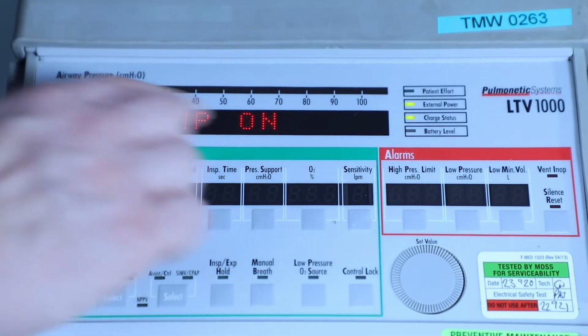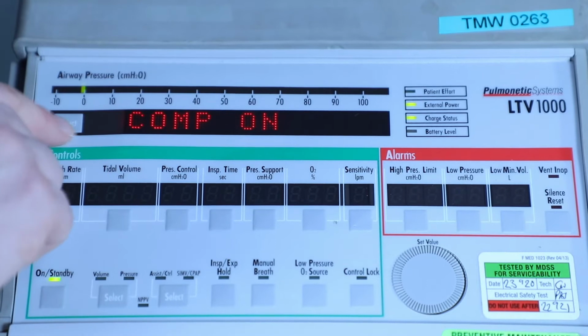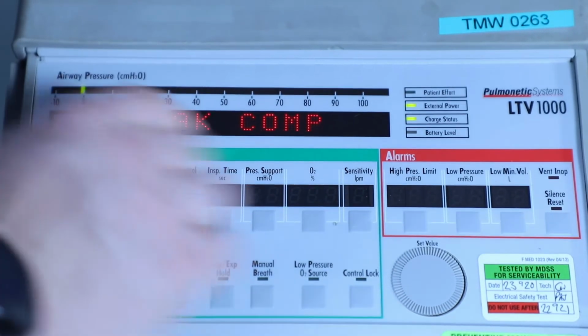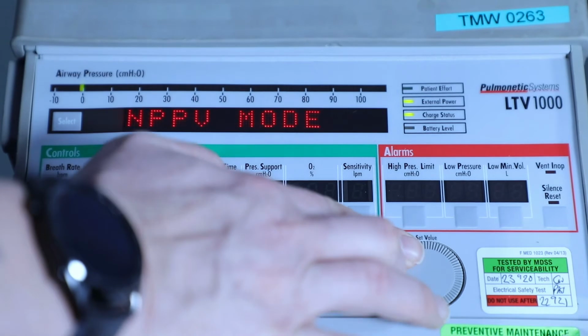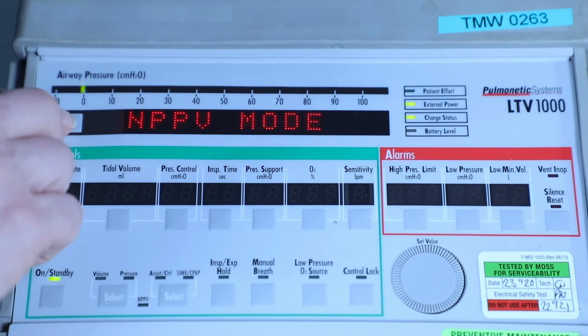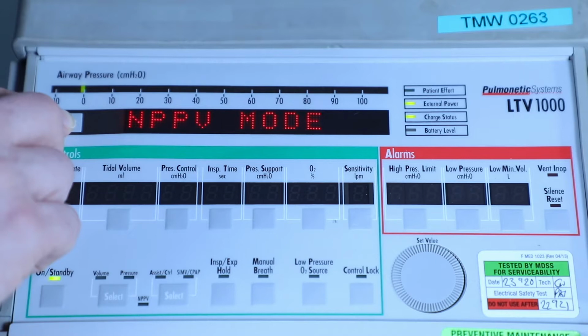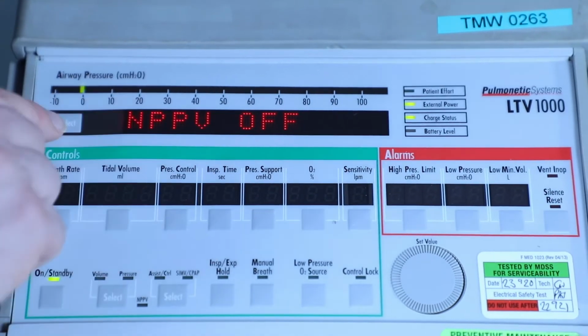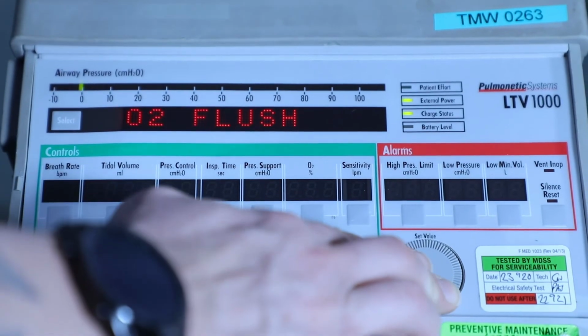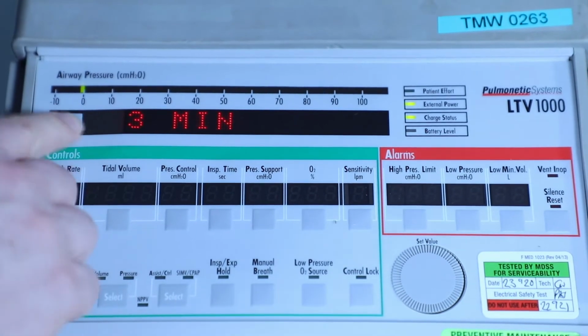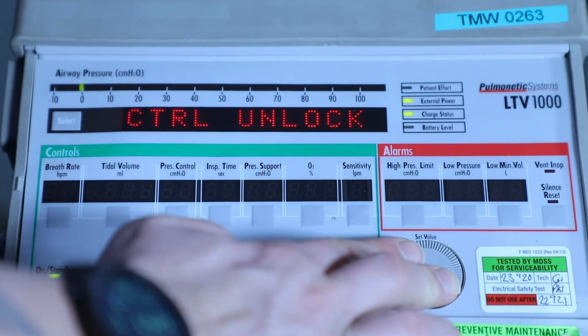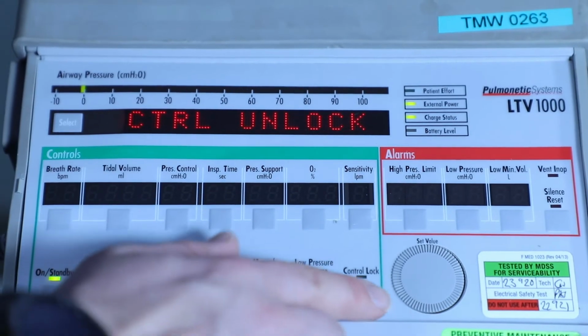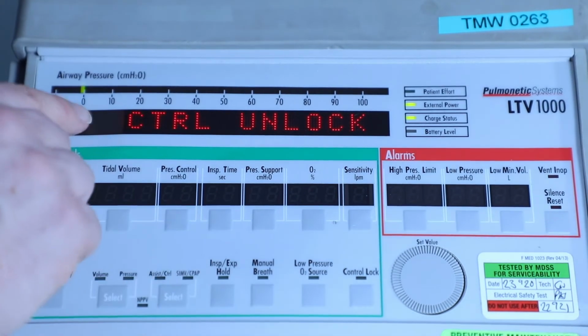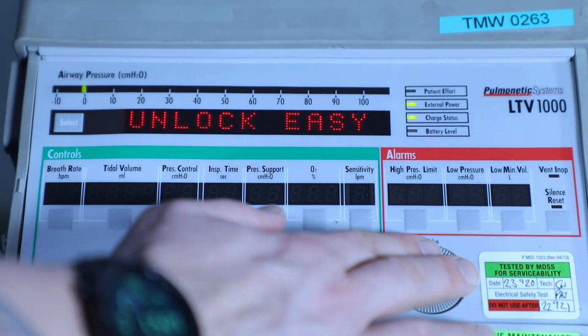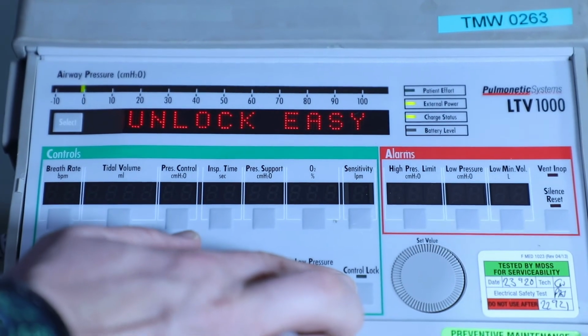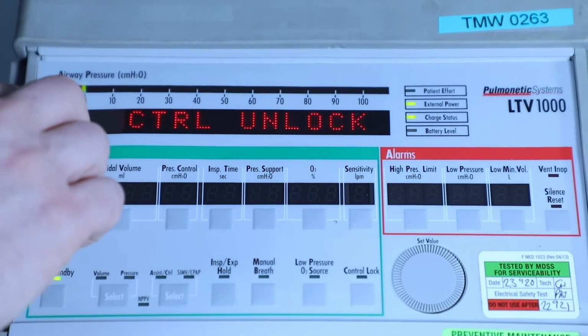Leak compensation is on. The LTV will compensate for up to 6 litres per minute. NPPV mode, so non-invasive positive pressure mode. This is set to off, and we don't use this for CCAST. O2 flush set to 3 minutes. Control unlock is the key that we use to lock and unlock the keypad. We have it set to easy. It can also be set to hard, which just means that you have to press and hold the control unlock for 3 seconds in order to unlock the keys.